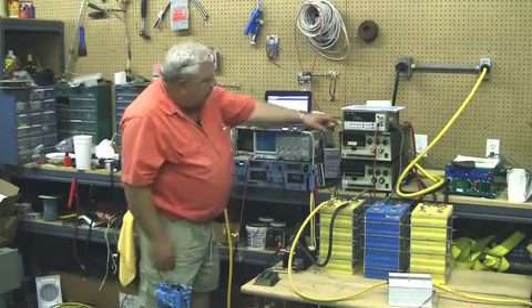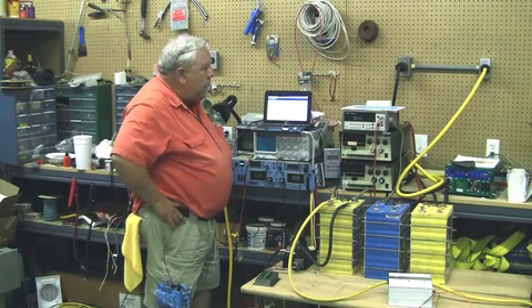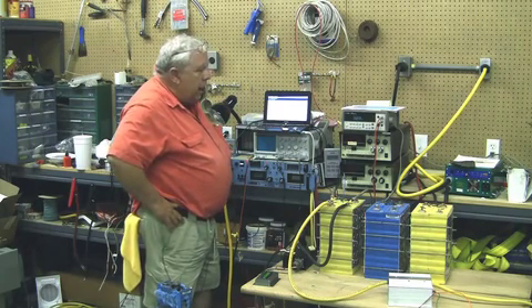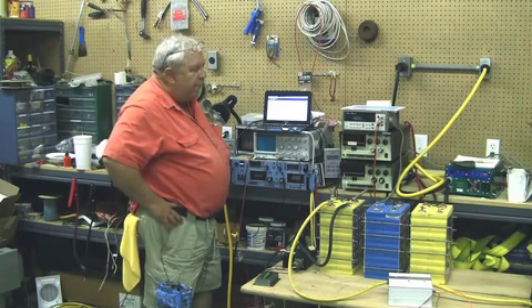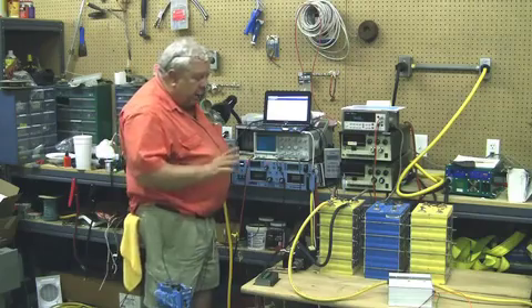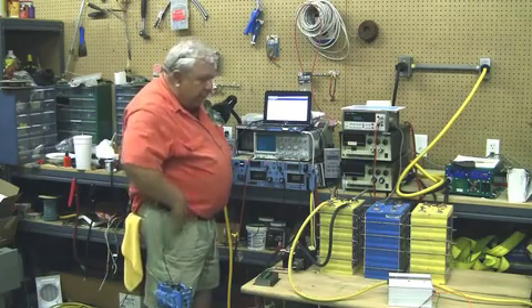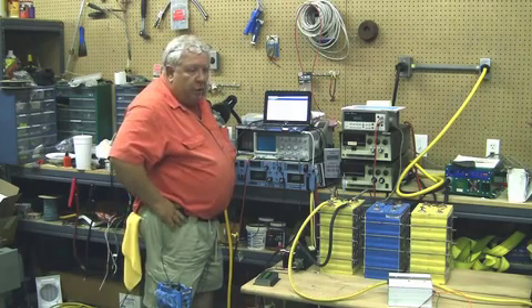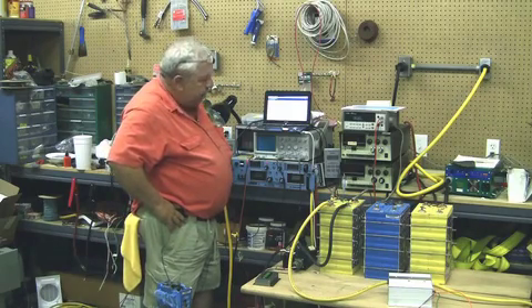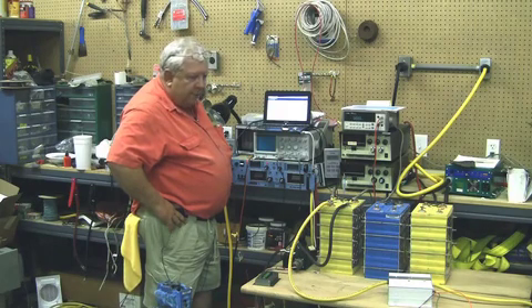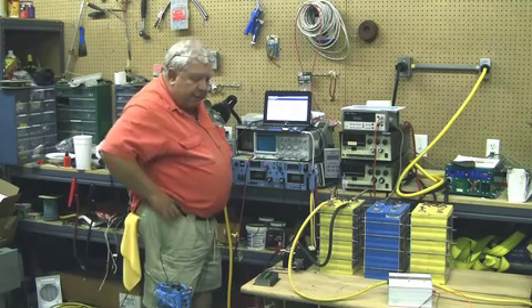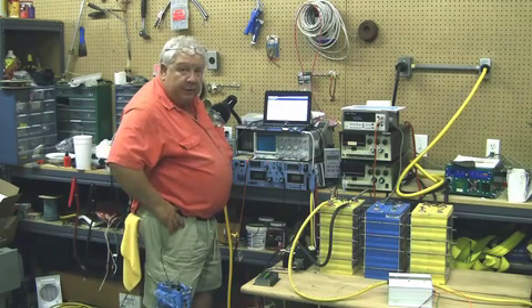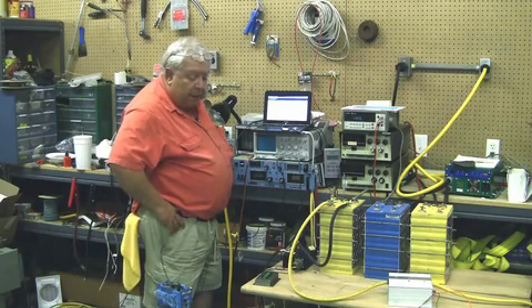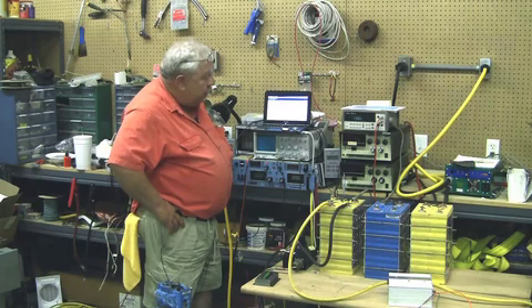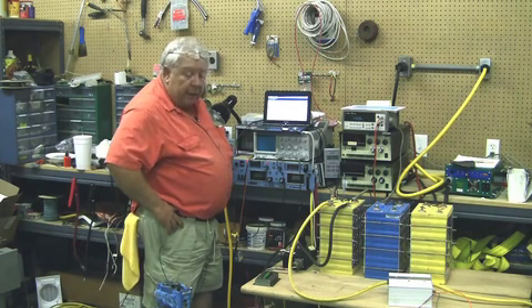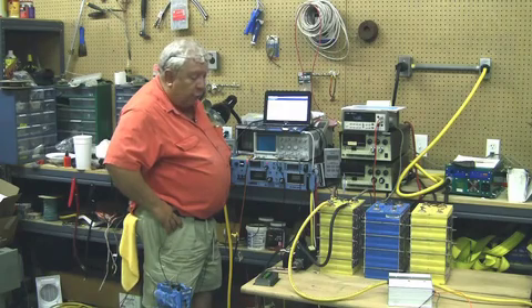If we watch this, this cell will start to fall over the period of about an hour, hour and a half, it'll get down to about 3.35 volts per cell. At that point, if I wanted to, I could put on, in this case, a 100 amp charge, or even a 50 amp charge, and do my constant current, constant voltage curve, and top that cell out quite nicely. But we've basically taken 197 amp hours out of the cell. We've put them back in, and we're at 100% charge. And we did that in an hour, basically, at a 200 amp hour rate.